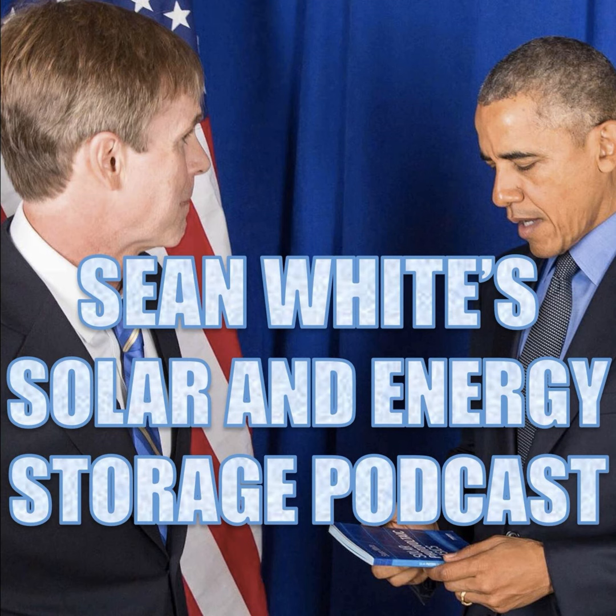It's crazy. So here it is, 80 to 20%. We just go 80 minus 20, that's 60% usable capacity. We're going to do some math with that a little bit, but the derating factor is 0.6. You want to find out how many batteries you're going to use. If you only want to use that much of your battery, then you would divide by 0.6 and increase the size of your battery bank.